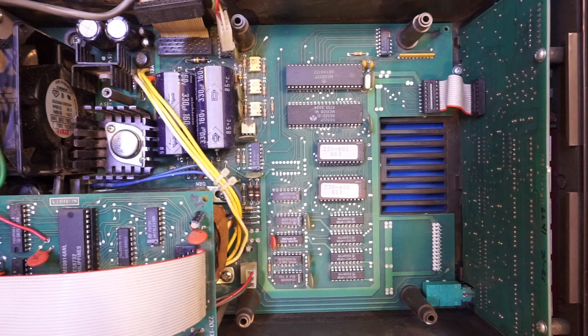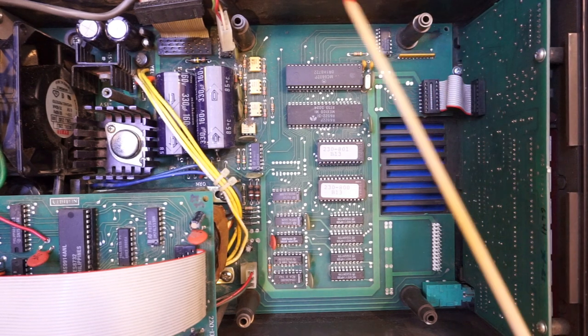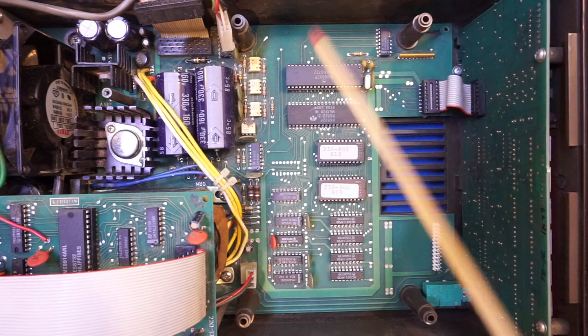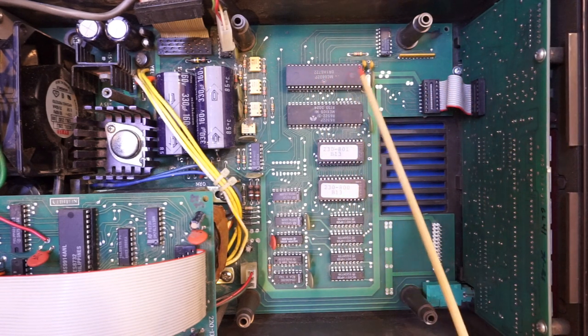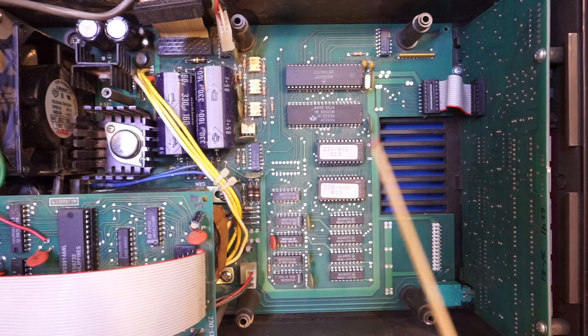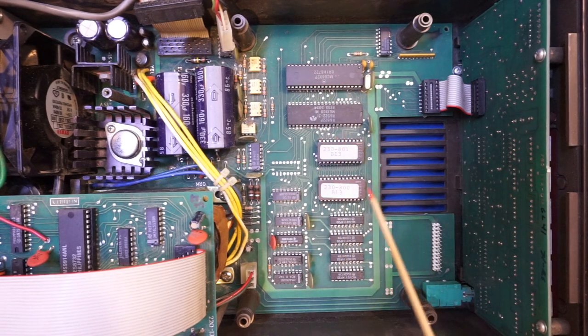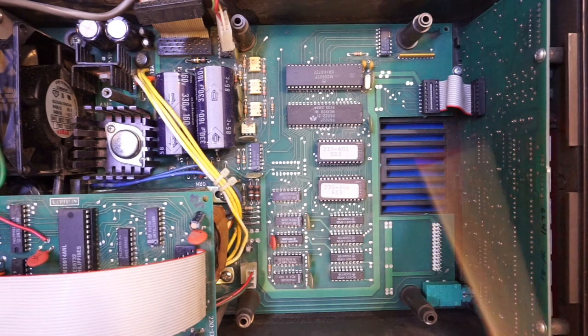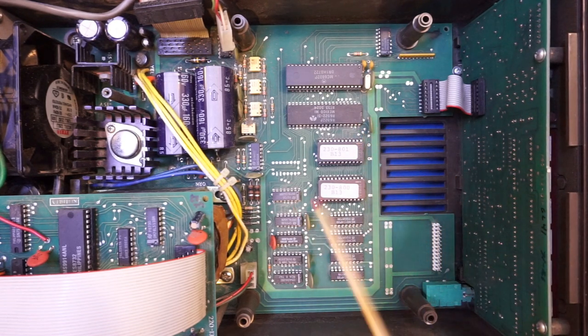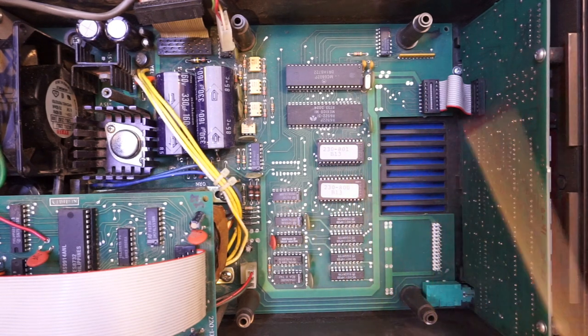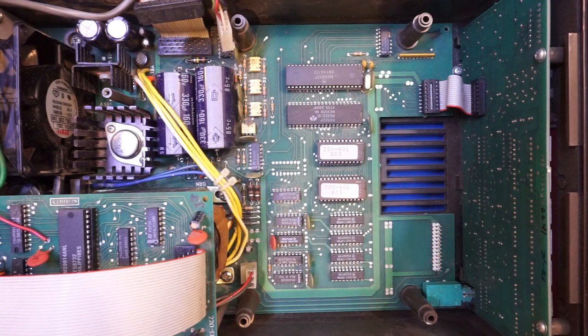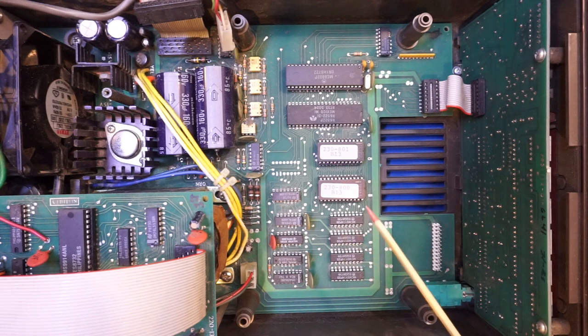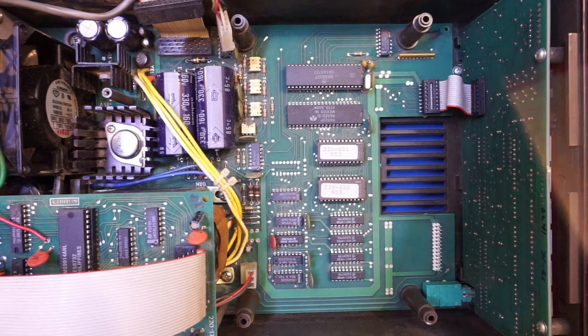And what we're looking at here now is the digital board and the power supply board underneath that analog board we saw earlier. And here, for example, you see that we have the main microprocessor as the MC6802, which is socketed. And we have a couple of firmware EPROM. Actually, speaking of firmware, I probably am going to take this out and make a copy of them and post it on my website. So for those who are interested and have similar versions of the Keithley 230, you can certainly use that to refresh your firmware.